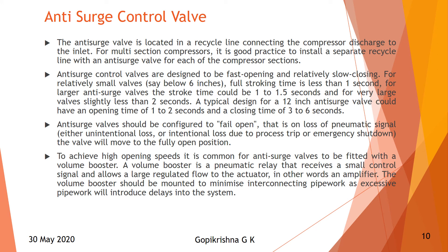For relatively small valves — for example, 6-inch — the full stroking time for open and close is less than 1 second. For a large anti-surge valve, the stroke time will be 1 to 1.5 seconds, and for a very large valve, less than 2 seconds. A typical design for a 12-inch anti-surge valve could have an opening time of 1 to 2 seconds and a closing time of 3 to 6 seconds.